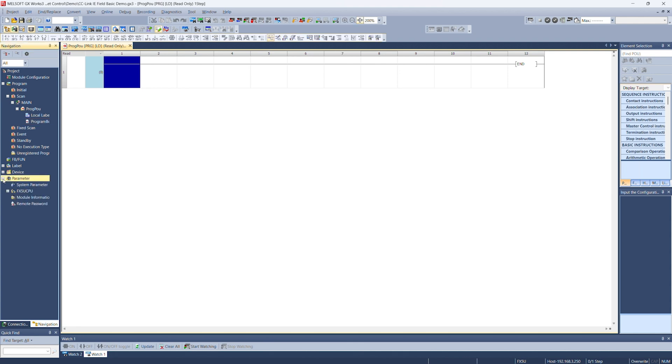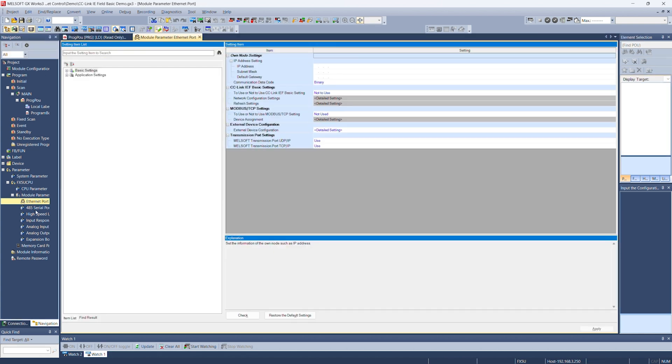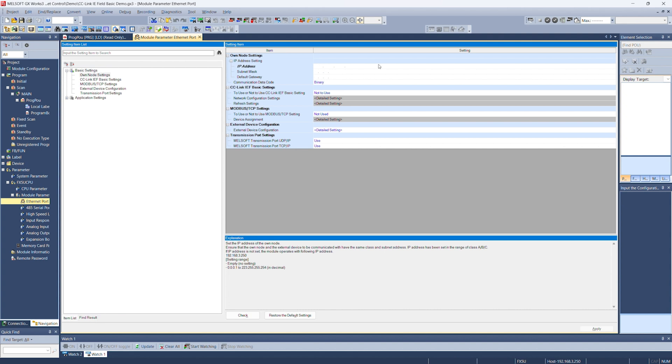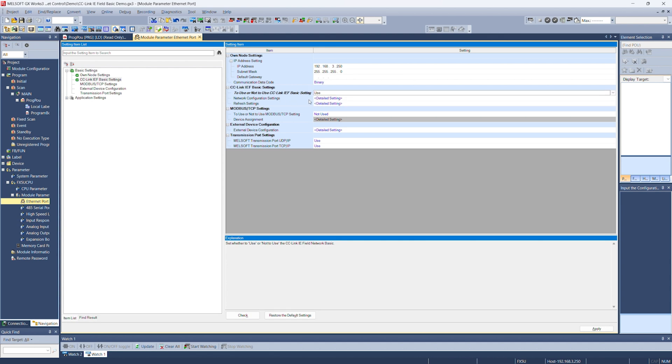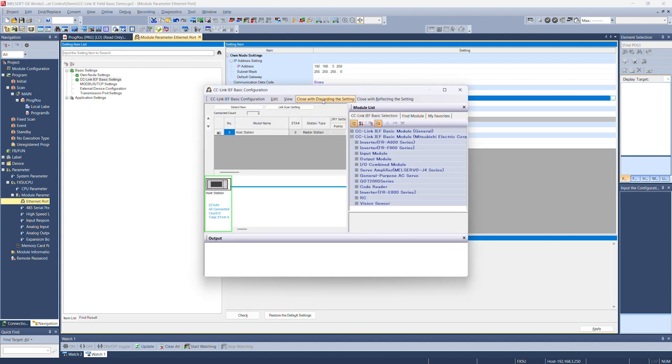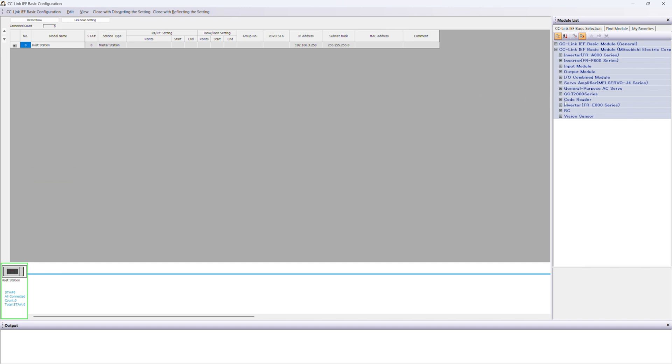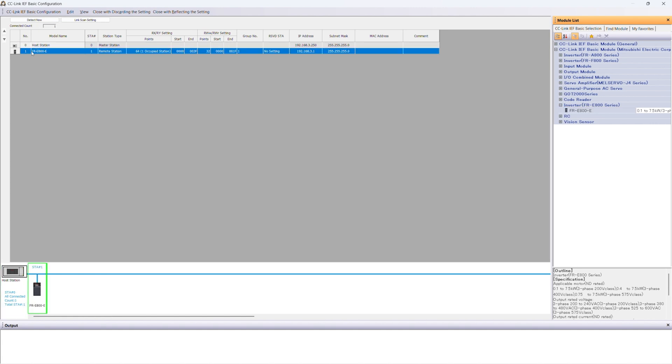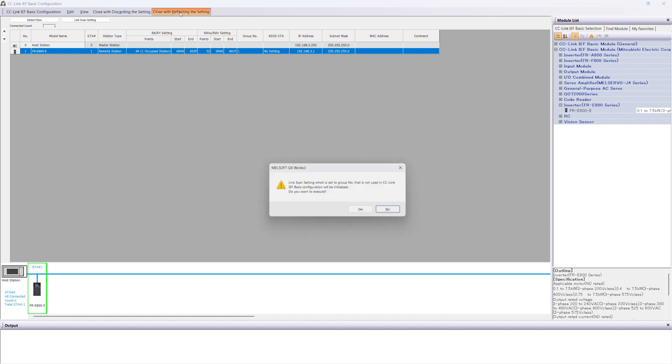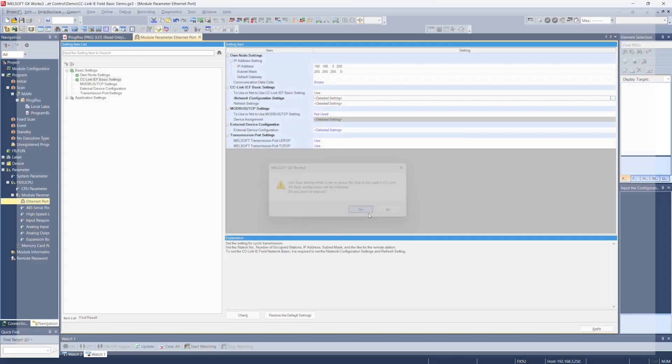Open up your project if you saved it, or a new one, we didn't get far. Again, parameter, FX5U CPU, module parameter, Ethernet port. We're going to set up the IP address of the FX5U CPU 192.168.3.250. And then subnet mask of 255.255.255.0. To use or not to use CC-Link IE Field Basic, we want to use it. Network configuration settings. Now, you should have the FR-E800 available if you didn't before. I'm going to drag and drop it next to our host station here. We can see in this table that we have now an FR-E800. And we should confirm that the IP address is the same as the one we set before: 192.168.3.1. Everything looks good. We're going to close with reflecting the setting. Click yes.